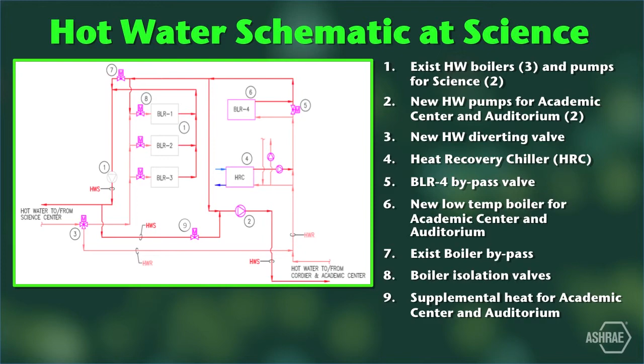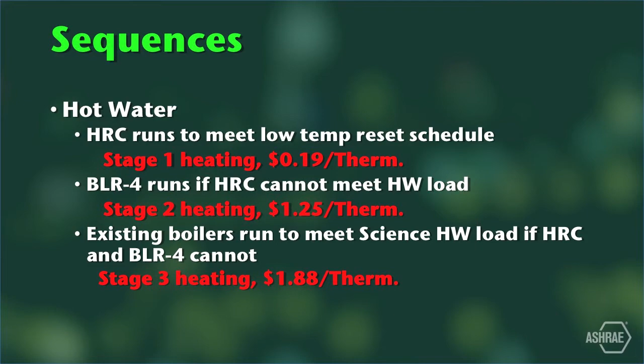With the holistic approach, we end up with three stages of heating for all three buildings, and they're arranged by cost. The objective is to minimize the operation of the science high-temperature boiler plant. A good energy conservation measure is always to run the heating system as cool as safely possible, which is easily done if you know the position of the hot water control valves. We don't burn gas unless there's no heat to recover, and we don't run the big boilers unless a condensing boiler running at a much lower temperature cannot keep up.